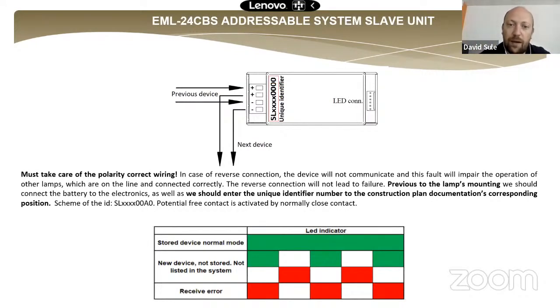We can see the unique identifier sticker near the power connection points. It starts with SL, 2 letters, and the next 8 digits will show the address of the light. That one we have to write down during the installation, and this ID will be read by the panel. And we have a LED connection point on this driver.